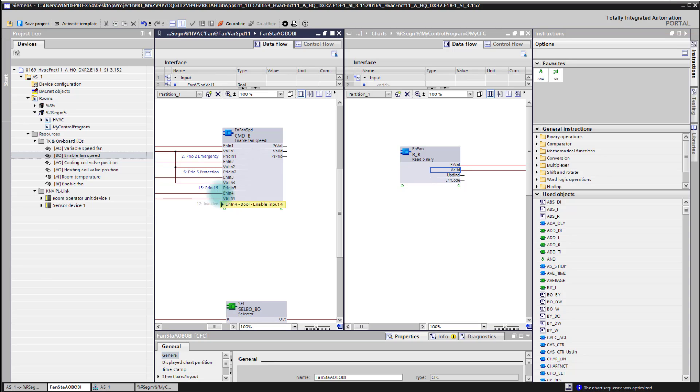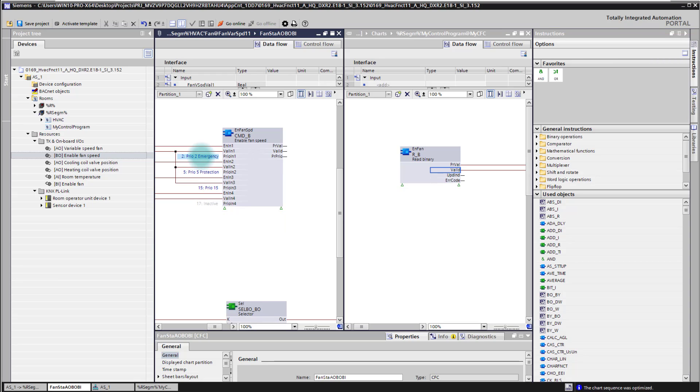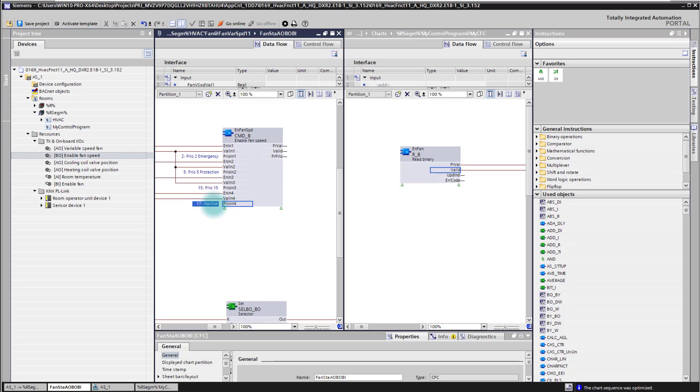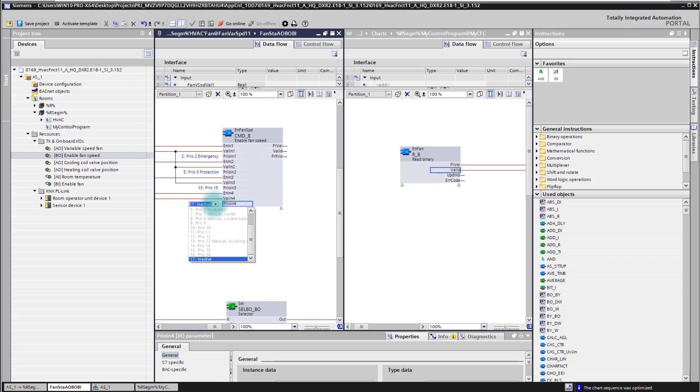And at the end of the day I can here then define also the priority which I want to use for that input. As you can see we have on that fan speed already three priorities used. We have an emergency priority which is used in the standard application, we have a protection, and we have a priority 15. Let's assume we want to now change it to priority 13 manual building user. This is just an example. You can also go with other priorities here. So that's it.